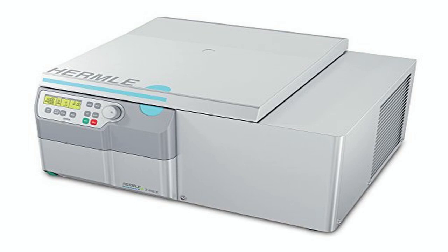The downside is that you're limited to swing-out rotors. The unit doesn't accommodate fixed-angle rotors that some protocols prefer for pelleting very small particles. If your lab's SOPs are built around a fixed-angle workflow, you'd either need to retrain staff or stick with a different centrifuge.